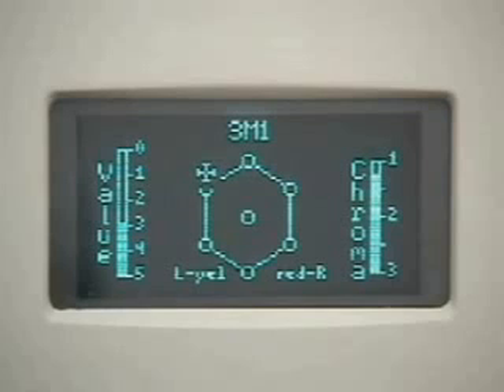The resulting 3M1 shade is the most accurate despite the advisory cross cursor being located over the yellowish hue 3L1.5, located at the top left-hand side of the 3-value shade group. These shade groups are arranged from 1 to 5 and are displayed on the left-hand side value bar. On the right bar, the chroma is shown as a plus 0.1 chroma variant, which EasyShade has rounded up to 3M1, as such subtle differences have little visual influence.